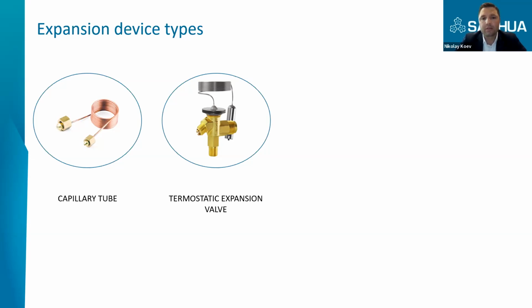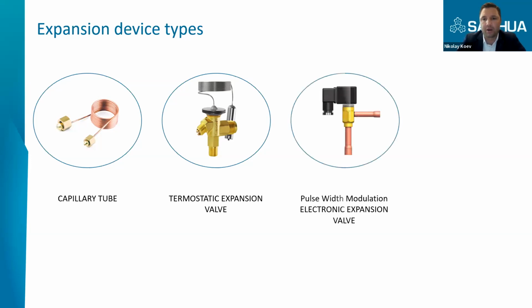And they're also limited in terms of pressure differential, which means that they cannot work properly at a very low condensing temperature. And you also may know that the lower the condensing temperature, or the lower the ratio between the condensing pressure and evaporating pressure, the more efficient the system. So the devices which are able to cover these requirements, to work at a very low superheat and at a very low condensing pressure, are actually the electronic expansion valves.